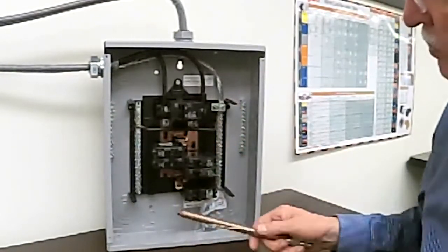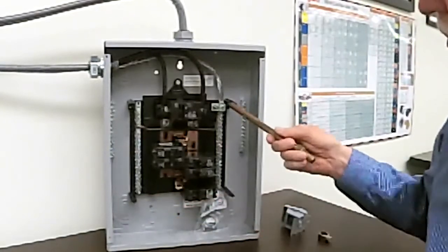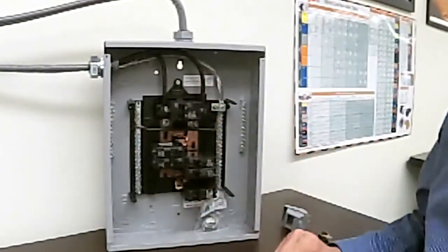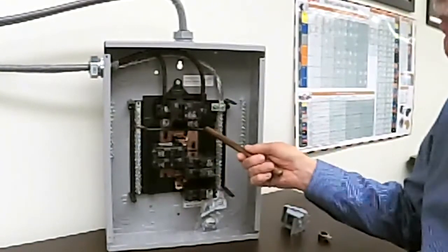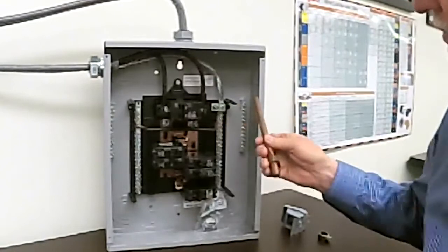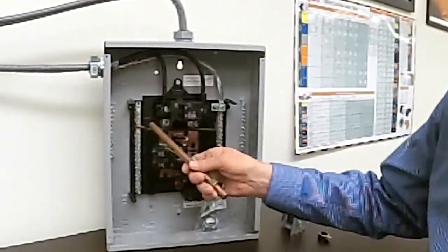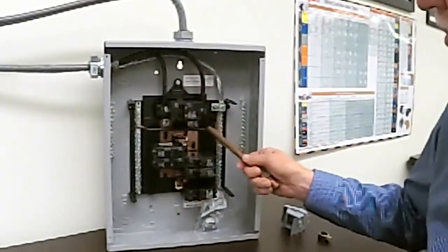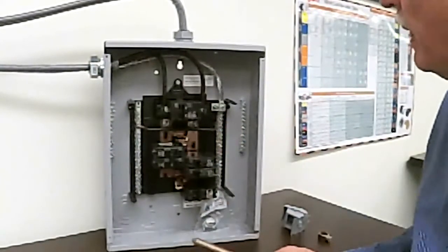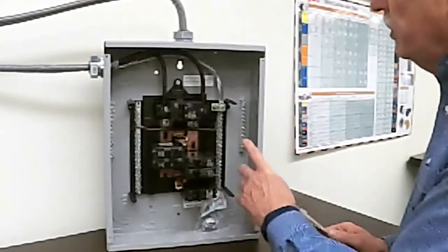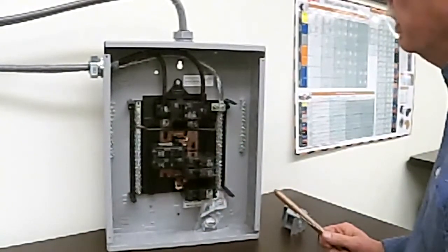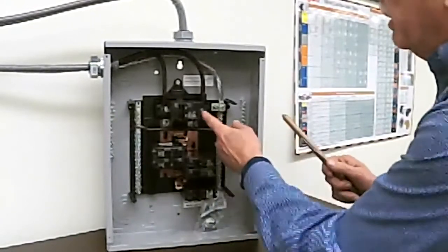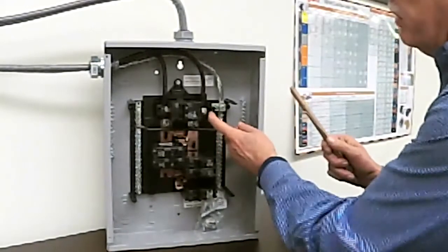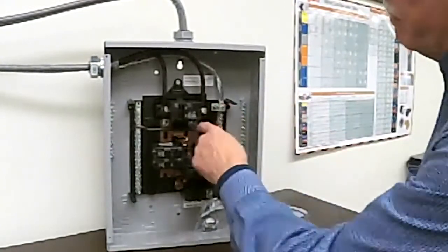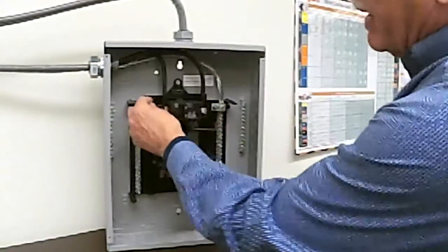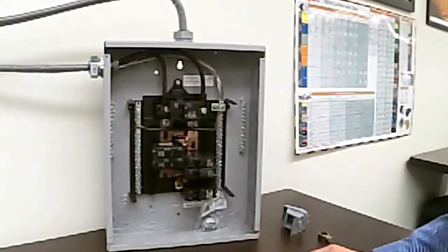Now, other panels do have a jumper bar across the bottom or one that goes in the back. I understand that. And they're made to be removed. But this guy is not meant to be removed. So don't remove it. They give you plenty of ground bar connections over there and plenty of neutral connections here. There's no reason to take this bar out. The other thing here is the new finger safe protection that the manufacturers are putting in. And that's here at the main lugs. And you can see that they have these plastic pieces that will protect you from accidentally touching the lug.